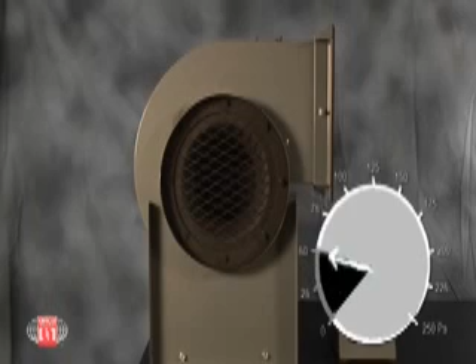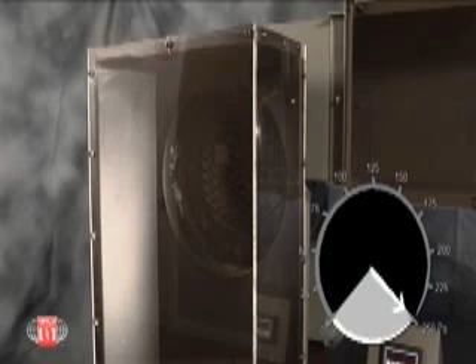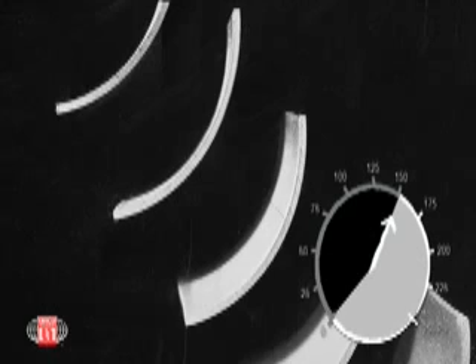Let's assume we use an open inlet as a benchmark, with the inlet dynamic pressure set to 250 pascals. If we affix a poorly designed right-angle inlet box directly to the inlet side of the fan, our dynamic pressure is reduced to 150 pascals, a 40% reduction, which equates to a 23% loss of airflow. If we improve the design by adding turning vanes to the inlet box, we improve the dynamic pressure to 190 pascals, but that's still a 13% loss of airflow.